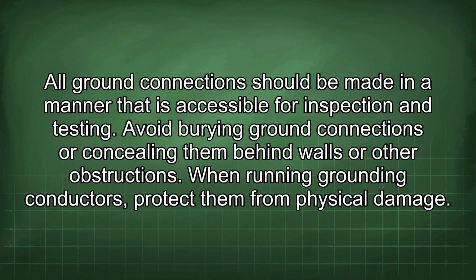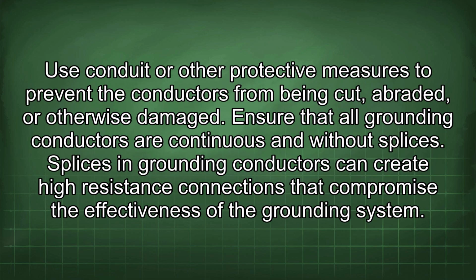All ground connections should be made in a manner that is accessible for inspection and testing. Avoid burying ground connections or concealing them behind walls or other obstructions. When running grounding conductors, protect them from physical damage. Use conduit or other protective measures to prevent the conductors from being cut, abraded, or otherwise damaged.